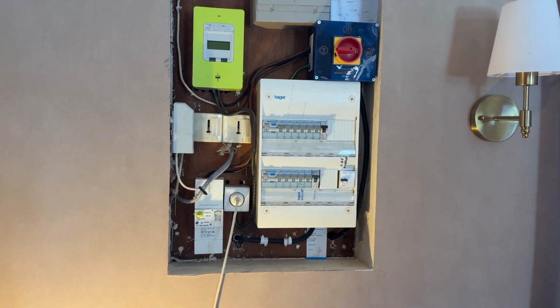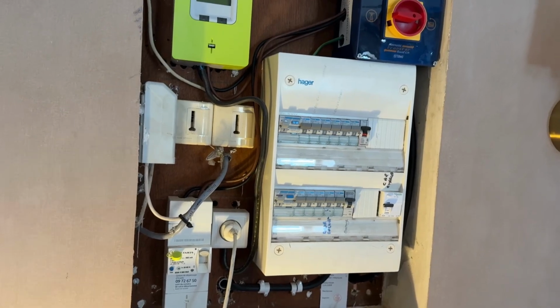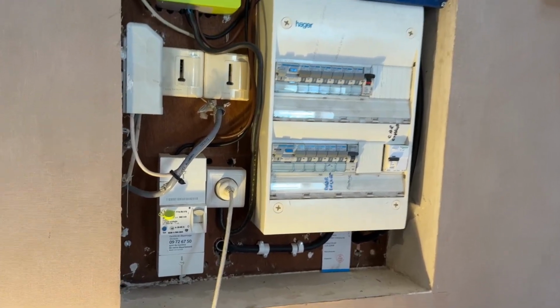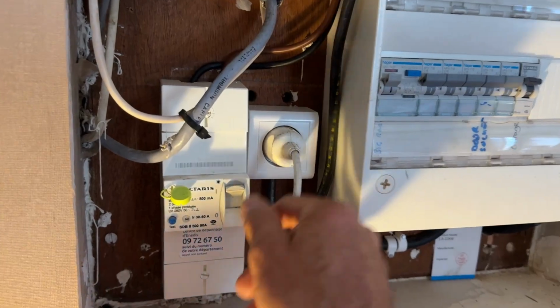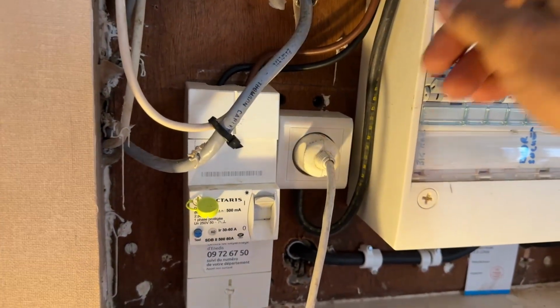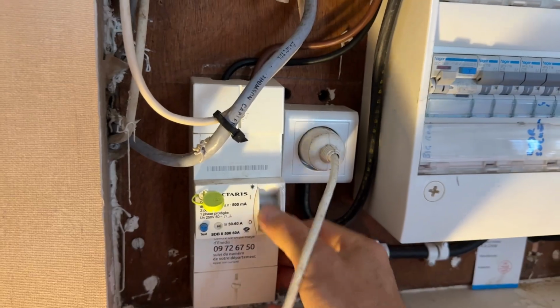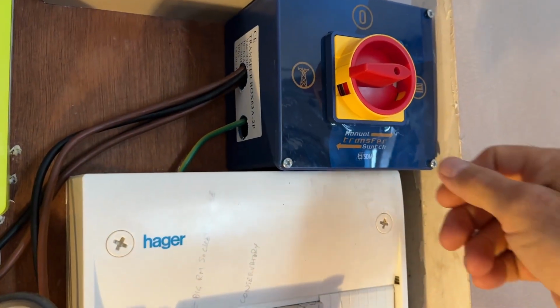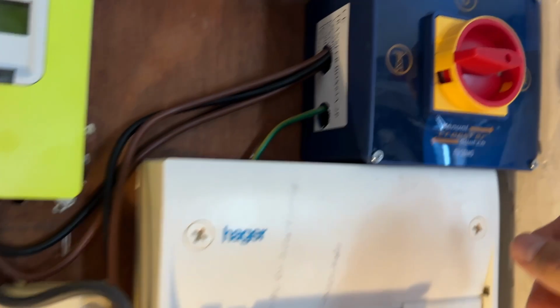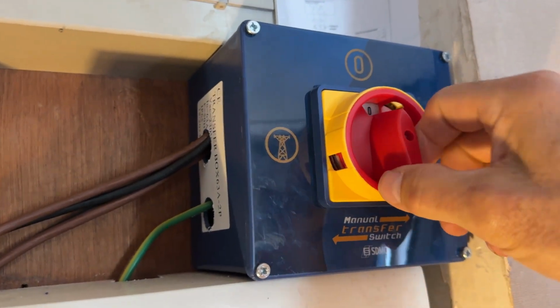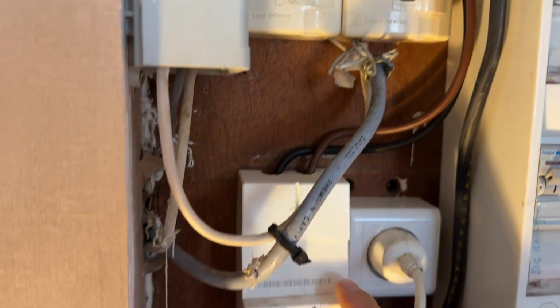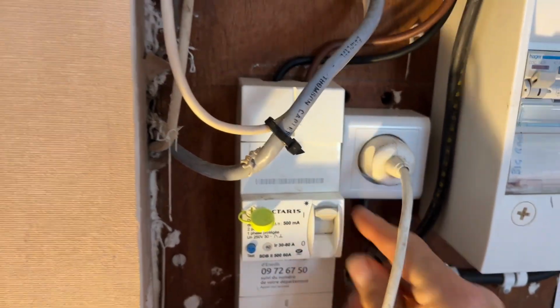Okay, so the generator's going. We can see that we've got mains power into the house because the light is on. So we're going to do the reverse, basically, of the procedures we used. So cut off the main, open the main circuit breaker to the house. Right now power from the generator is going through this. We're going to shut this off. There's no power in the house now except through this socket, which is direct to the mains. Switch this back to the mains and close this circuit breaker. We've now got mains power back in the house, and now we can turn off the generator and we can disconnect it.